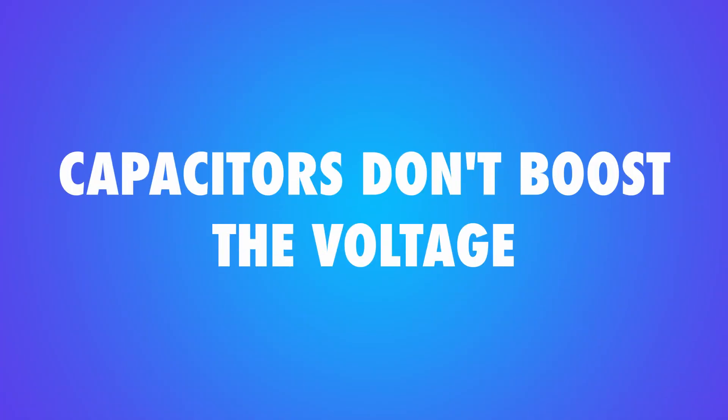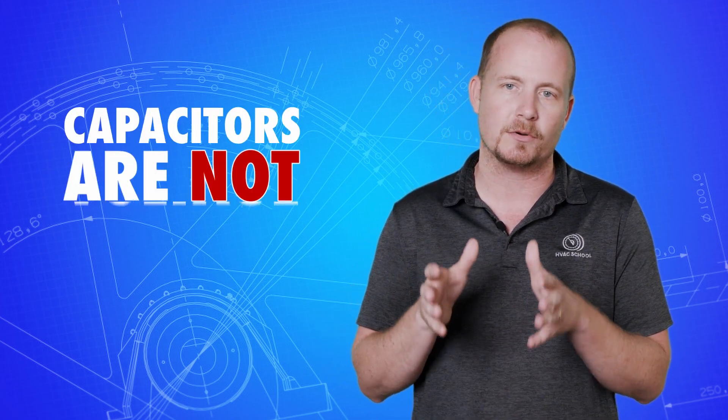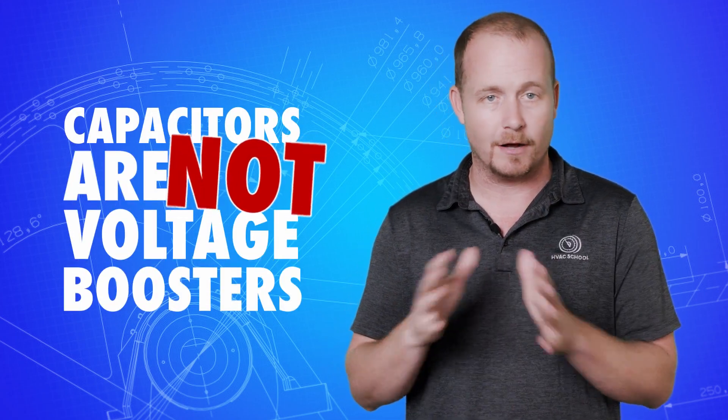Capacitors don't boost the voltage. A capacitor is a device that stores a differential charge on opposing metal plates. While capacitors can be used in circuits that boost voltage, they don't actually increase voltage themselves. We often see higher voltage across the capacitor than the line voltage, but this is due to the back EMF or counter-electromotive force generated by the motor, not the capacitor itself.